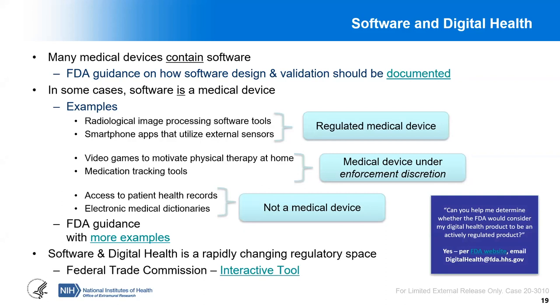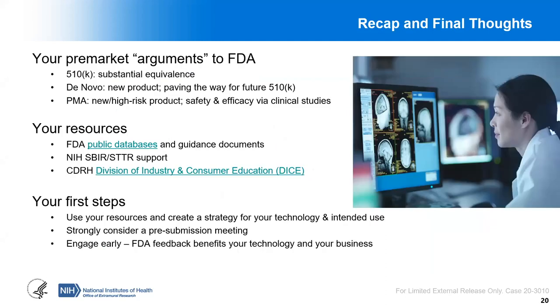FDA offers further support for developers in the digital health space. If you're asking whether FDA would consider your digital health product to be an actively regulated product, you can reach out to them directly with just that question through their email address. In recap, we talked about the three main pre-market authorization pathways at FDA — 510K, DeNovo, and PMA — and any of the three may or may not involve a clinical study that requires an IDE.